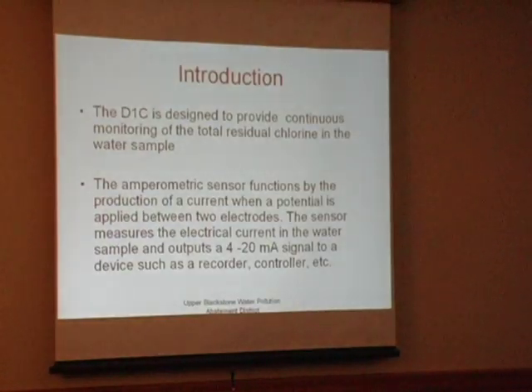The D1C, which is the model of this chlorine analyzer by Prominent, is designed to give you a continuous read of chlorine, whether it be free or total. In this case, it's total. As opposed to having to take grab samples or have a different type of sampling measurement system where it may be periodic, once every 15 minutes. This is continuous.